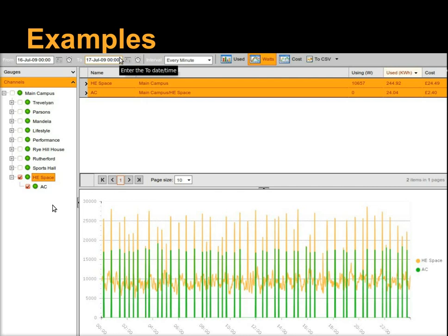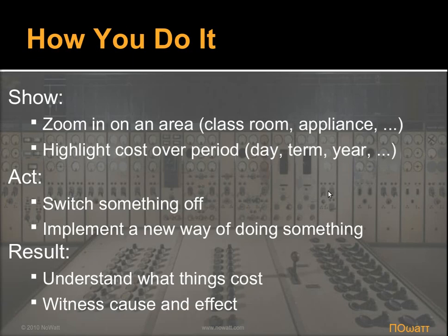I'm not sure what that's for, but it's not used very often, which you can see, it's got a constant load almost. But the software picked up this air conditioner, which was running 24 hours a day, and is responsible for 10% of the cost in that particular building. And when they looked at it over a longer period, it was on 24/7. So there's a 10% saving that they could have made, that in fact they did make, I believe. So there's a couple of examples.